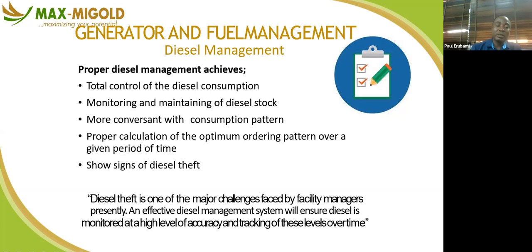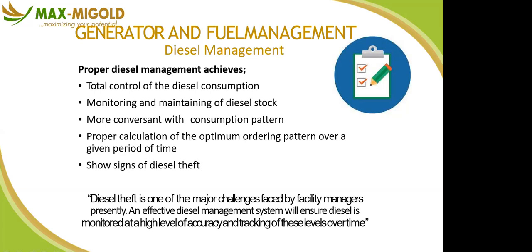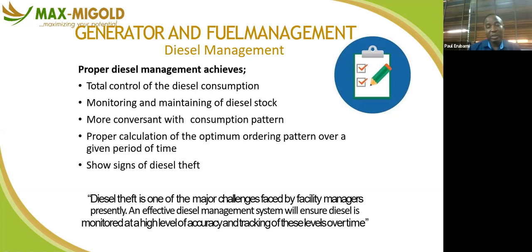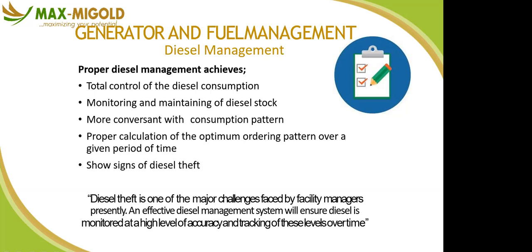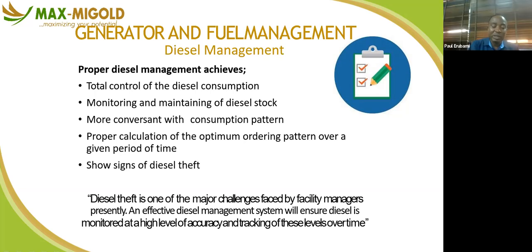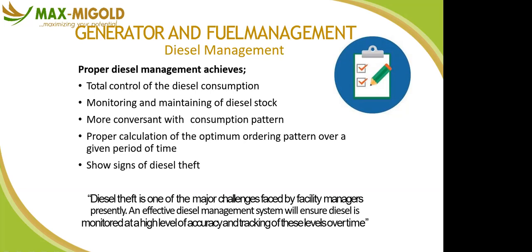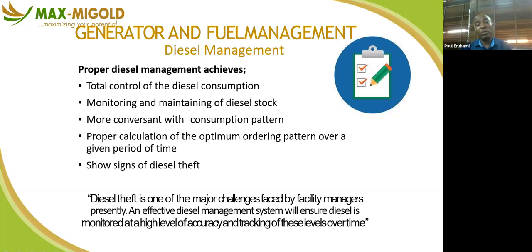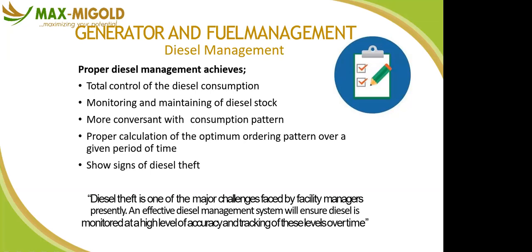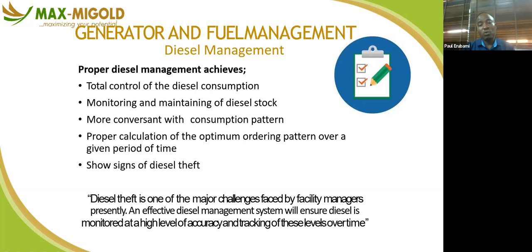So when you want to make a case, you can say, we don't need 2000 kVA to be powered at night. The load I have recorded over time is less than 500 kVA. I would suggest we go for a 350 kVA or 200 kVA for light load, when we are off peak and on weekends. Because you have the facts that you have registered over time, nobody will query you. After all, the management is looking for a way to reduce costs. Unlike when you don't have facts, they tell you, this is how we have been doing it. You are employed to bring value, positive value to your organization. So you tell the management, we don't need 2000 kVA at such a time. We need 100 kVA or 250 kVA. So we are saving costs for the management and it's justified. Nobody will query that.